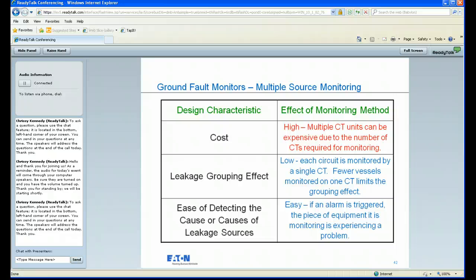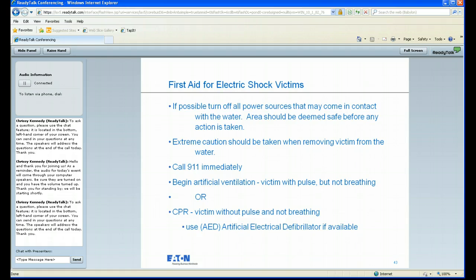From a leakage grouping standpoint, this is a very, very low effect. Each circuit breaker is going to have its own monitor, and it also makes detecting the cause or causes of the leakage a little easier to locate, because if a circuit breaker is tripped or an alarm is triggered, it's going to give you the exact location of where that issue is coming from, whether it be one or two boats or an individual circuit breaker. It's much easier to track that down through the multiple source monitoring devices.